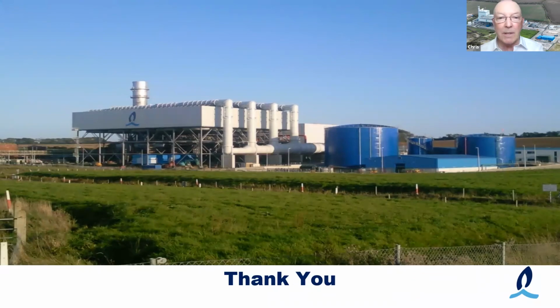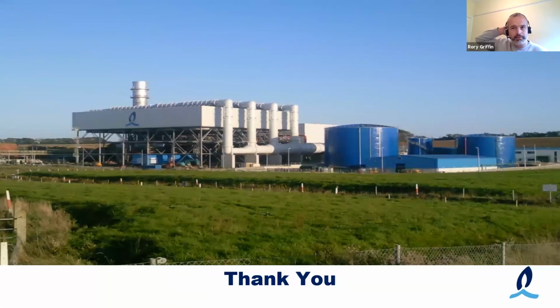I just have a question myself in relation to the electrical end of it. You mentioned earlier you had 2 feeds coming into Whitegate, 2 from ESB. If you have one of those out for maintenance, what's the situation then if you had a failure on it? Do you have an alternative supply ready? If one feeder is on maintenance and the remaining in-service one trips, yeah, we're in trouble.